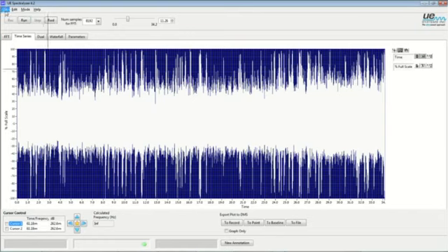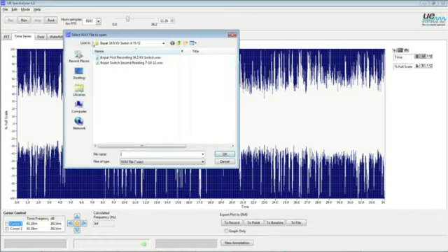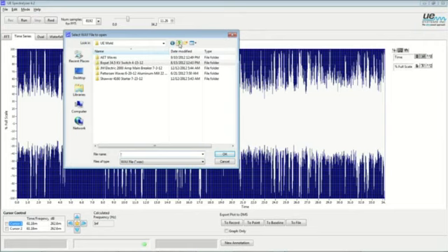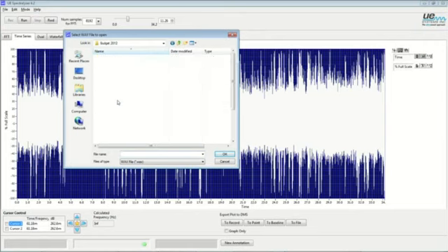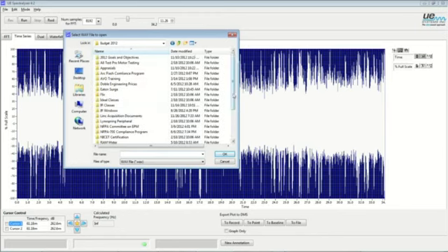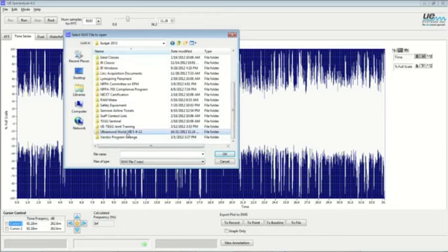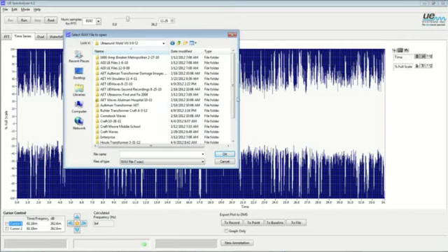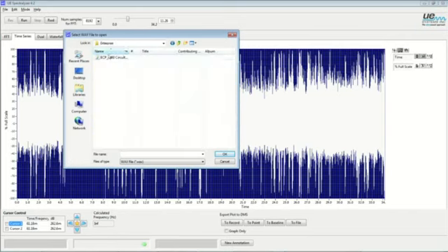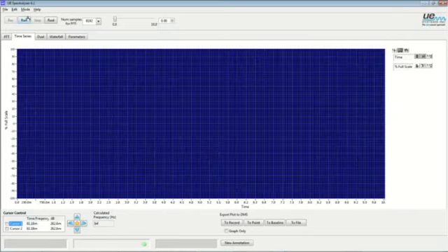A different type of tracking event here on a different voltage will demonstrate that. This next one is actually on a lower voltage system, and I believe it is in this paper. This is on a 20 amp circuit breaker in a 208 volt system. So it's an internal tracking fault on a circuit breaker feeding a server. I'll let this play first, and then we'll talk about it.